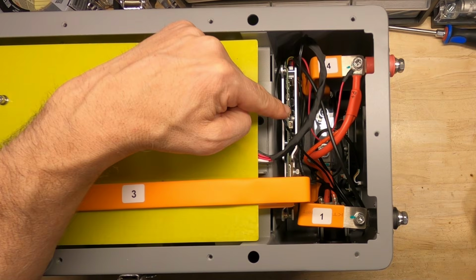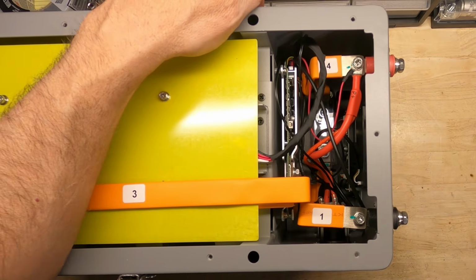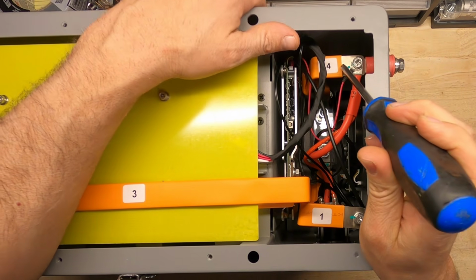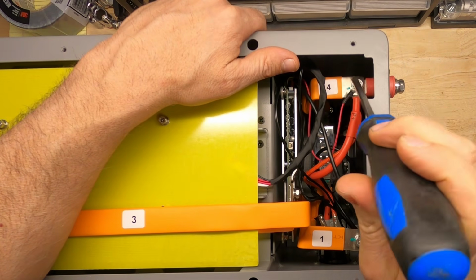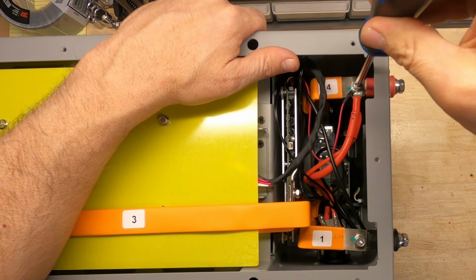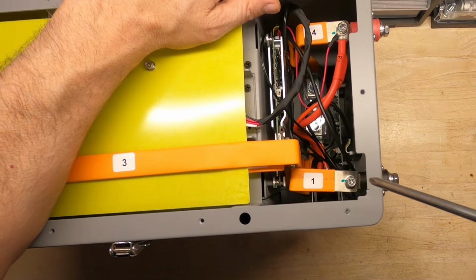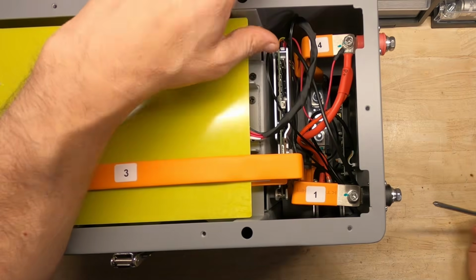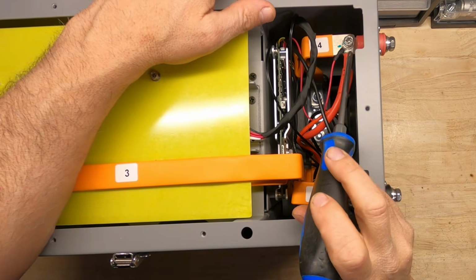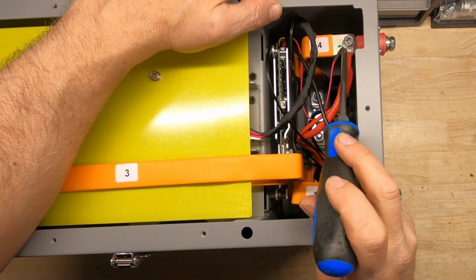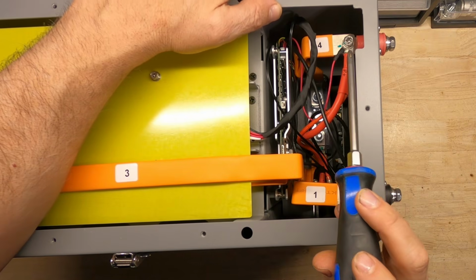Okay, looking inside the BMS compartment, we see the same bus bars that we've seen on other batteries, and the M6 screws torqued and marked on both sides, so that's nice. You can see we have 2 lugs plus the bus bar.